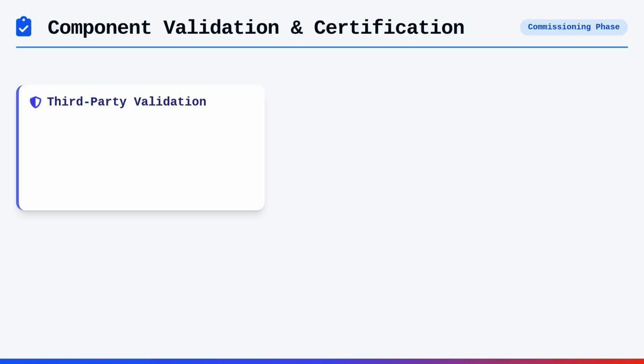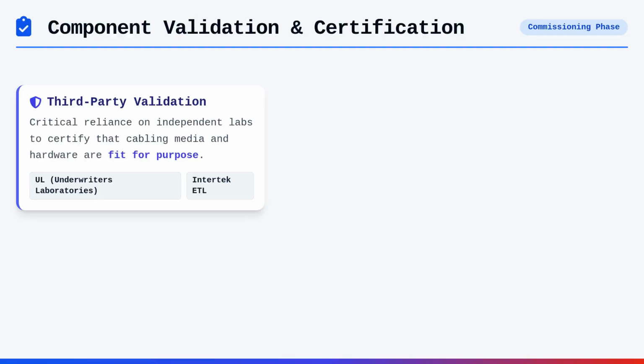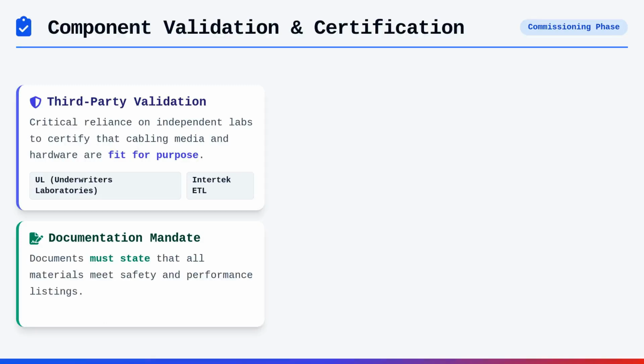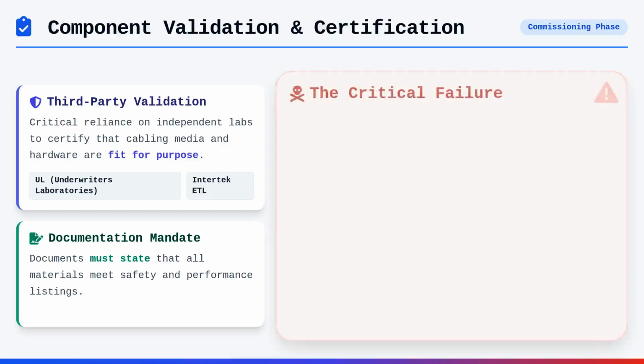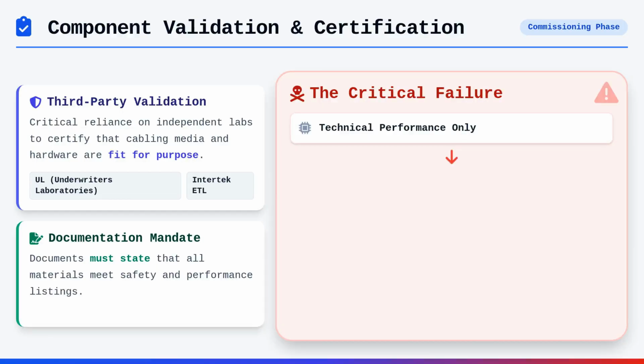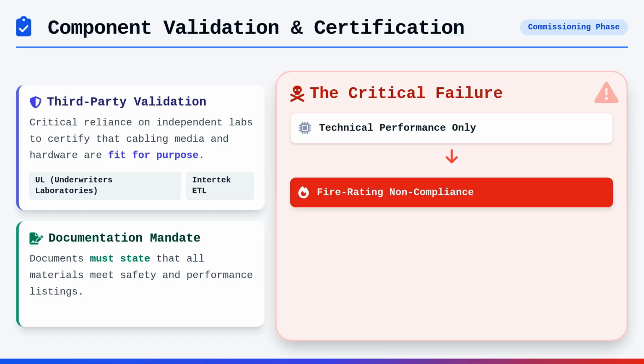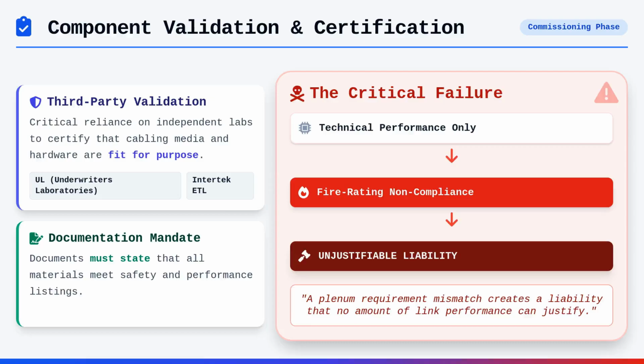Validation of components is another critical area where designers often fail during the commissioning phase. We rely heavily on independent testing laboratories such as Underwriters Laboratories or Intertek ETL to certify that our cabling media and hardware are fit for purpose. When specifying products, your documents must state that all materials meet the necessary safety and performance listings. A common mistake is selecting a path or a connector based solely on technical performance without verifying fire rating compliance. If you specify a cable jacket that does not meet the plenum requirements for an air handling space, you are creating a liability that no amount of link performance can justify. Rigorous documentation of these listings for every device in your system is non-negotiable for project sign-off.